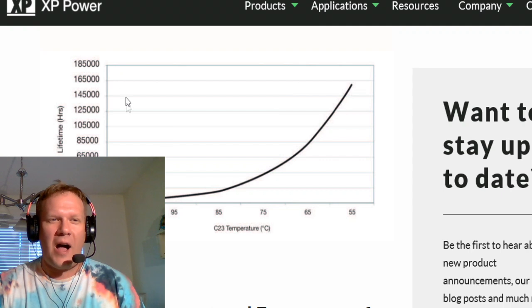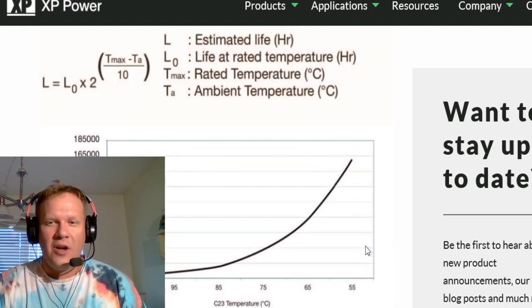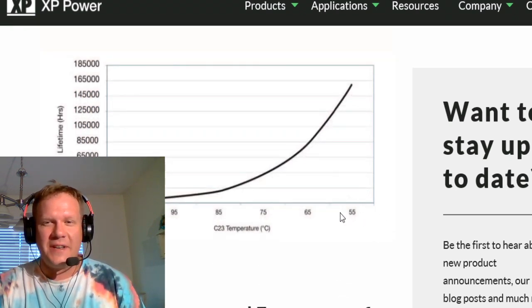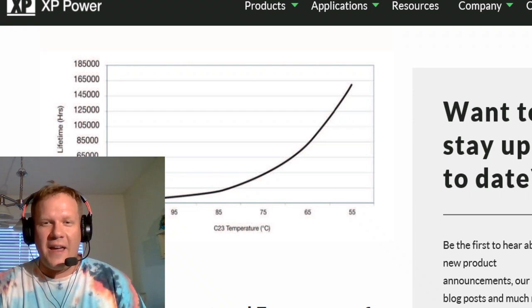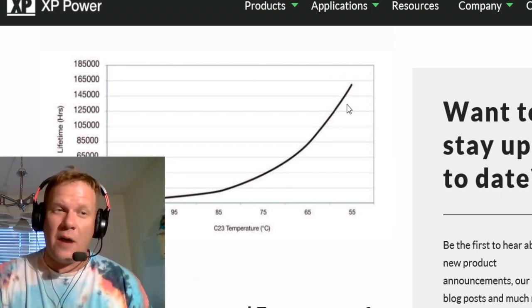And so that's why, if you follow this curve, you can see why some of the capacitors that are not exposed to heat, where they may be way down in this 55 degrees Celsius range, have a life expectancy of almost 150,000 to 160,000 hours of use.